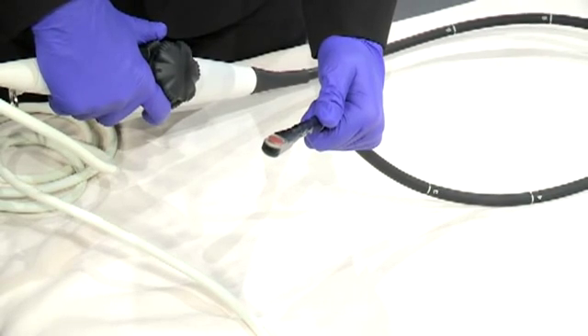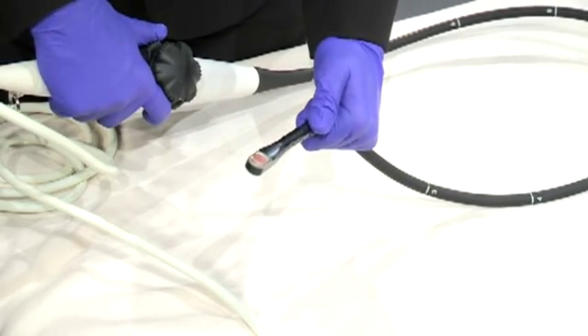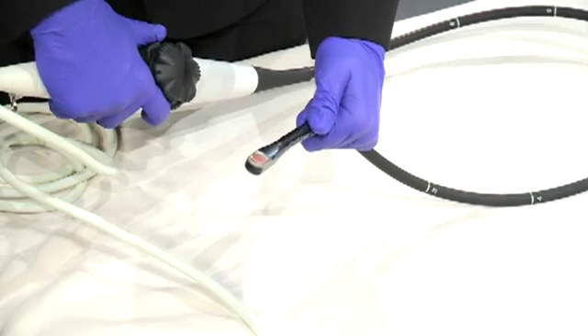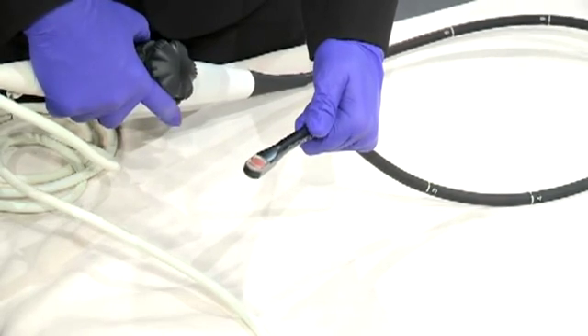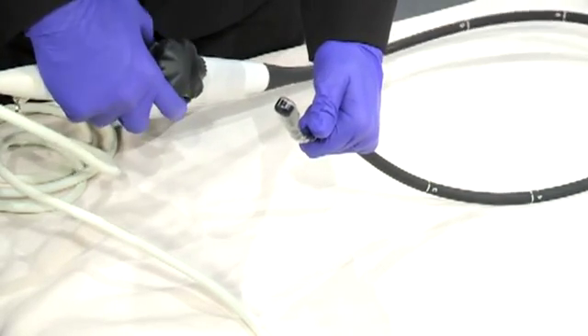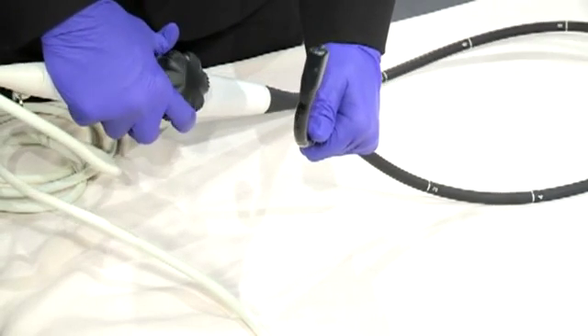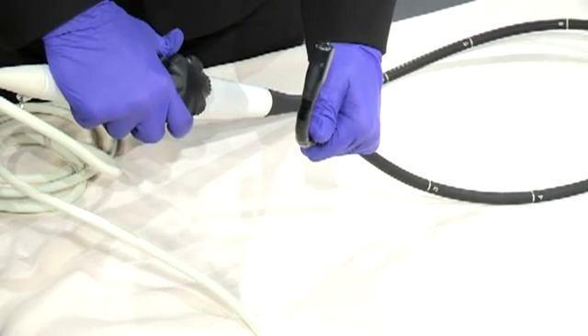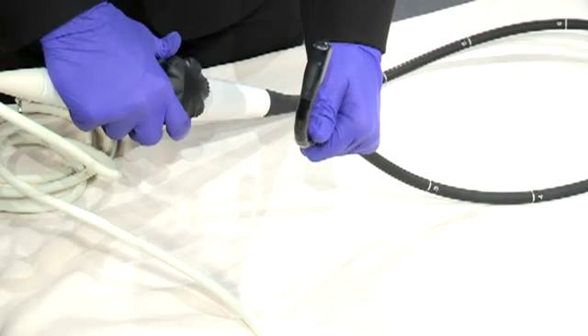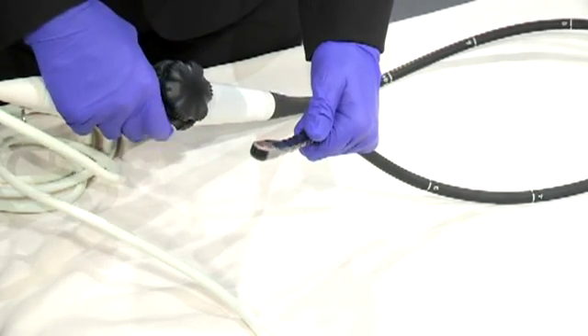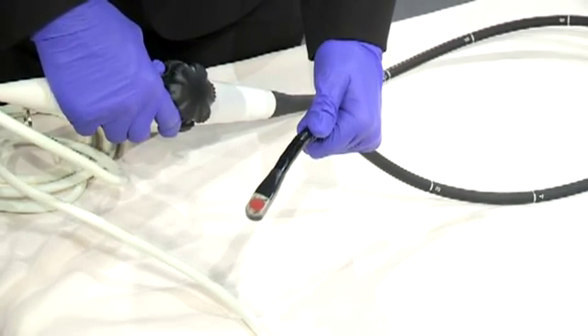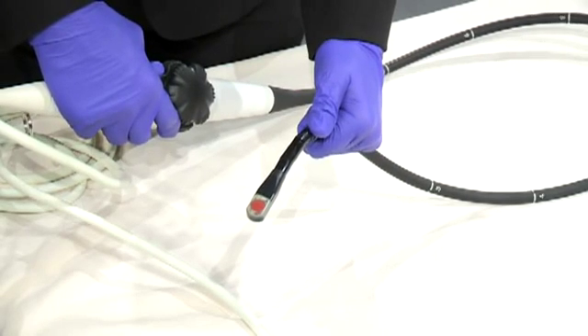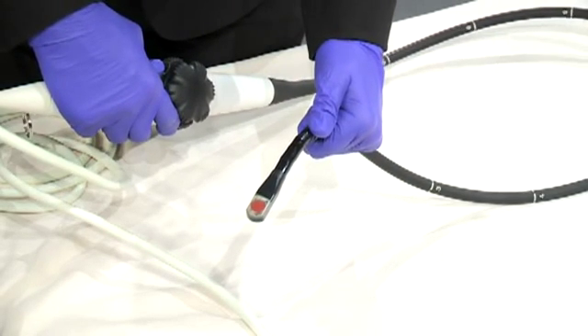When checking the deflection of the probe tip, carefully observe the deflection angle of the tip. Turning the lower wheel clockwise should deflect the tip of the endoscope into a range of 120 degrees with reference to the endoscope shaft. Turning the lower wheel counterclockwise will move or retroflex the endoscope tip downward to approximately 40 degrees angle.